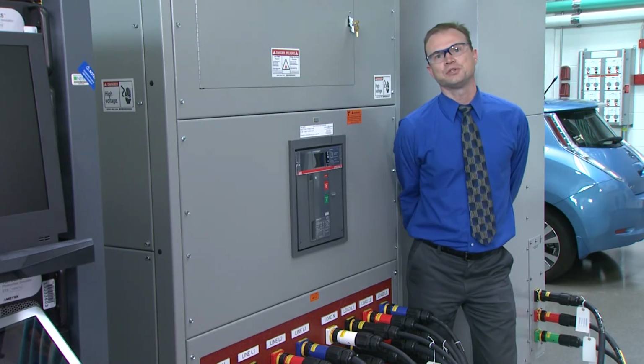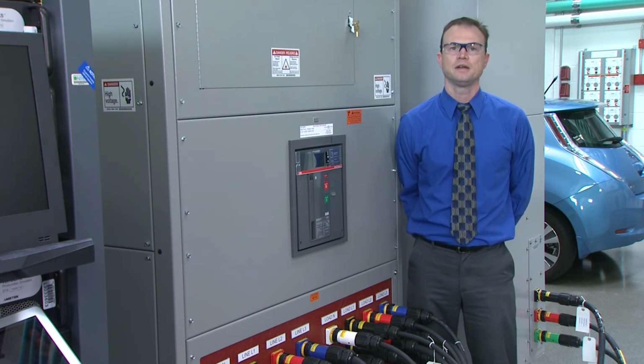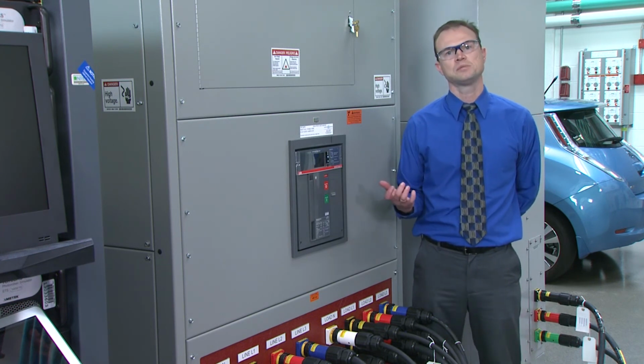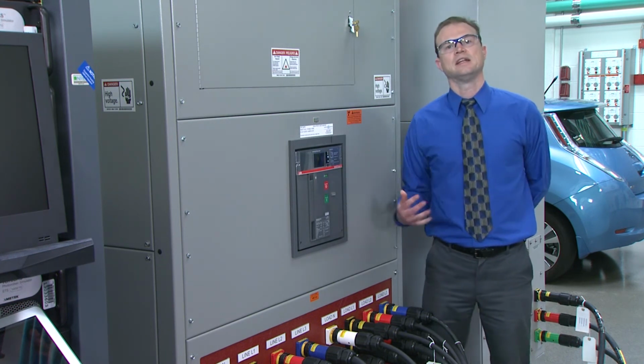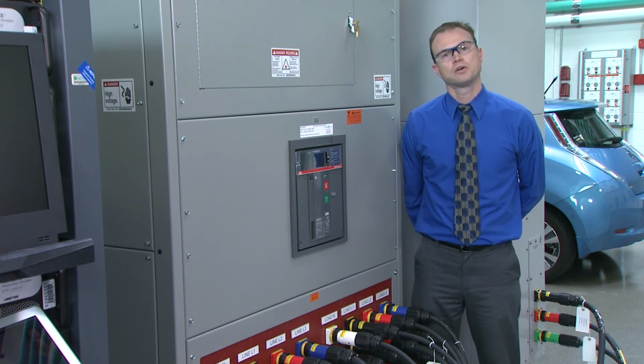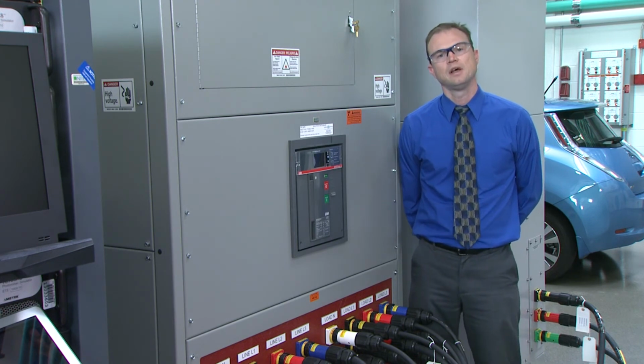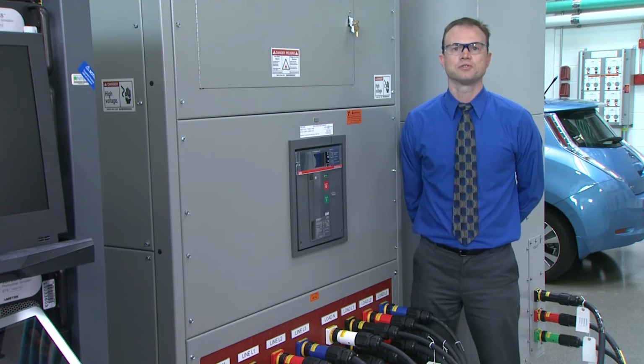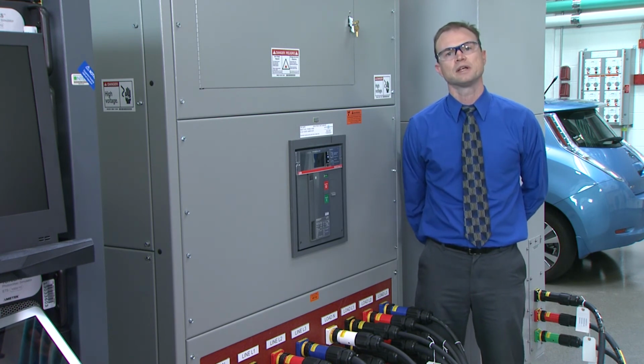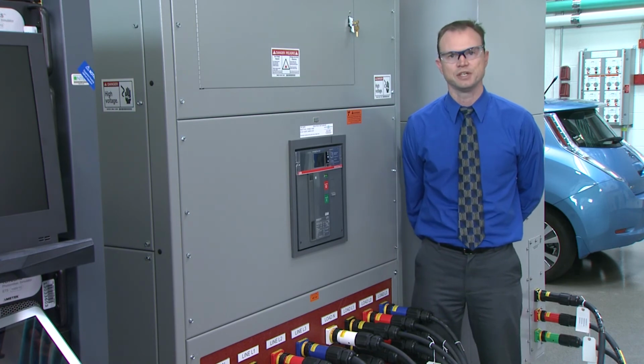As the final stop on our tour, this is our Microgrid Switch, which forms the boundary between our microgrid and the main utility grid. This has logic inside that can detect problems in the main utility grid and disconnect very rapidly. It also sends a signal to our master microgrid controller that it has to take over local microgrid operation. Then later, when the main power grid is restored, this sends voltage and frequency information to the microgrid controller so it can synchronize, allowing us to have a seamless transition back to grid-tied operation.